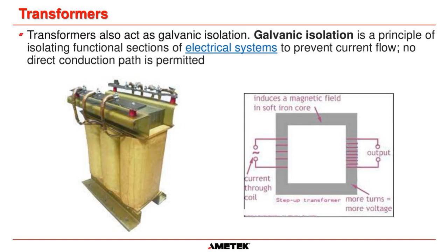Let's say you had a fault on your charger and DC managed to get back onto this winding here - well, DC cannot pass through a transformer, it has to be AC. So that prevents DC from propagating over to your AC input, which is connected to your MCC. This transformer will not allow DC to propagate onto your AC, which could give you serious problems. So that's the two reasons we use a transformer in our design.